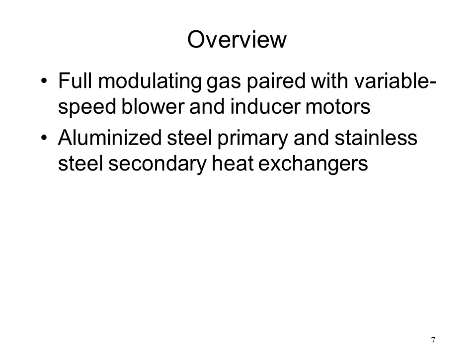So we've got a fully modulating gas valve, and it's combined with a fully variable speed blower and a variable speed inducer motor. So we got three things that are modulating here in conjunction with one another to get you the right heat transfer BTUs. We have two airflows, right? One airflow on the combustion side of the heat exchanger, one airflow on the space conditioning side of the heat exchanger, and then we have the gas flow that we're modulating.